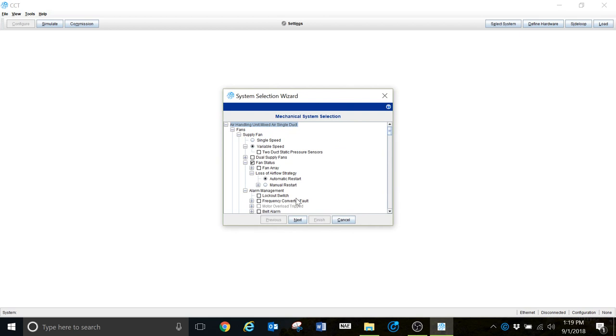This pop-up window gives us options for the air handler we're going to be programming. If you have a constant volume air handler — where it just pulls in a contactor from the controller and the air handler runs at constant speed — you would select that option. Variable speed is what we're going to be using if you have a variable frequency drive on your air handler. The variable speed static pressure control will use a static pressure setpoint to regulate the speed of the supply fan. We'll leave that default and leave fan status checked.